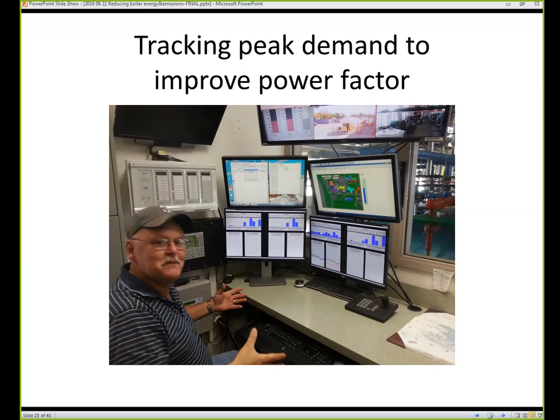Tracking peak demand, we do that. We track our natural gas coming in in case we had to go to oil, so we would be able to track exactly, and same thing on our peak demand coming in on electricity. Guys, if you don't have somebody looking at your bill, look at your bill every month and see what you're doing and track. Check out what your power factors are. The lower your power factor, the more money you're spending. Westar will be more than happy to come out and give you some advice on how to get your power factors up. Yeah, it's pretty big savings. Next.